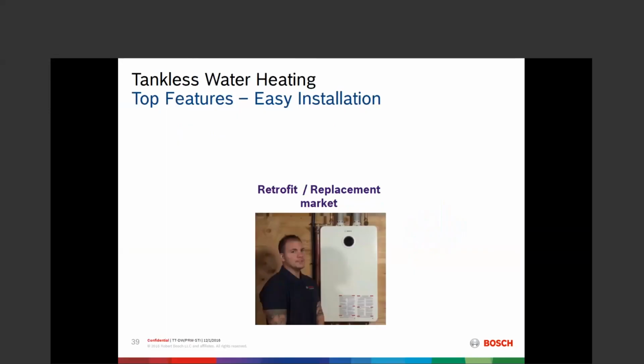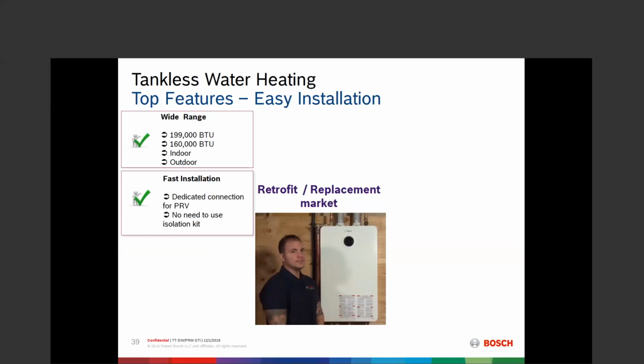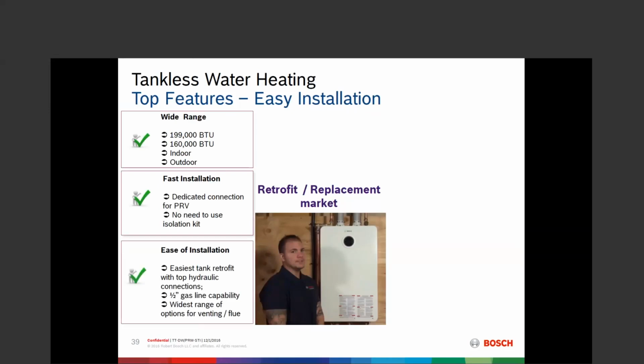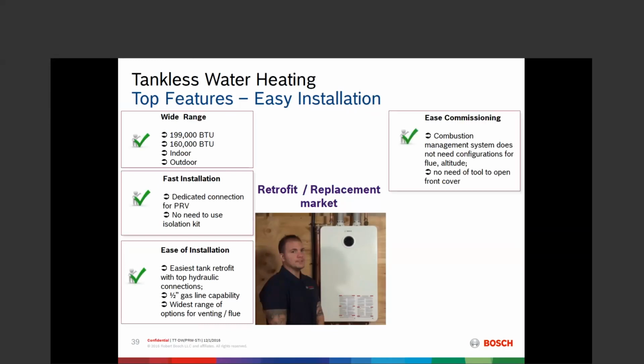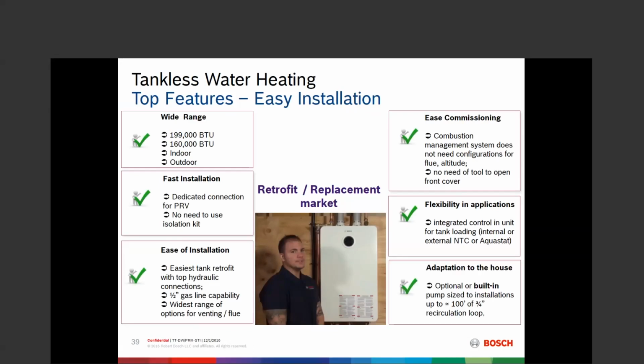So what do you do to make the job easier for the guy with the wrenches, the guy getting out of the truck and installing this thing? BTU range with all very similar installation characteristics. Performance can be different by BTU, but installation is going to be the same. It has a relief valve included. Easy retrofit of tanks with the top connections. Yes, we can attach it to a 1/2-inch gas line, assuming there's enough gas pressure to manage that. The combustion management system says we do not need a combustion analyzer. The unit can manage that for us. We can use this thing in tank loading applications, domestic recirculation, and the maintenance is a lot easier with the bottom built-in ports for descaling.